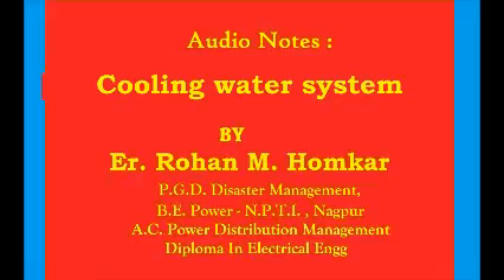Now, water cooling methods and the mechanism of cooling. The cooling of water coming out from the condenser is done either by a cooling pond or a cooling tower. The hot water gets cooled when exposed to atmospheric air. That is because the atmospheric air has a definite capacity to absorb water vapor at a given temperature, and the heat required for water vaporization is taken from the remaining water, and the water gets cooled.